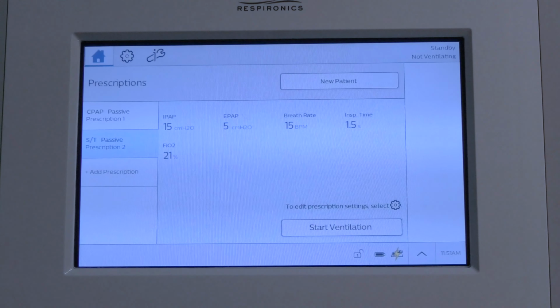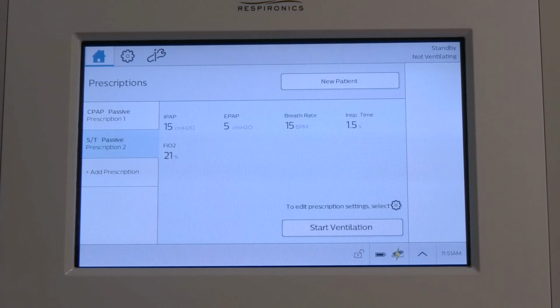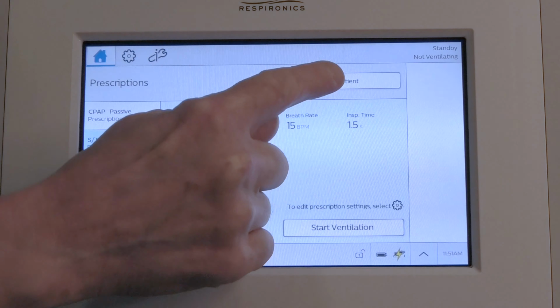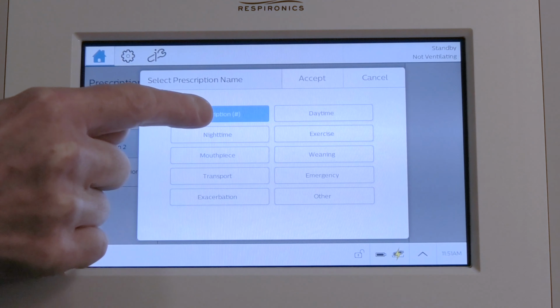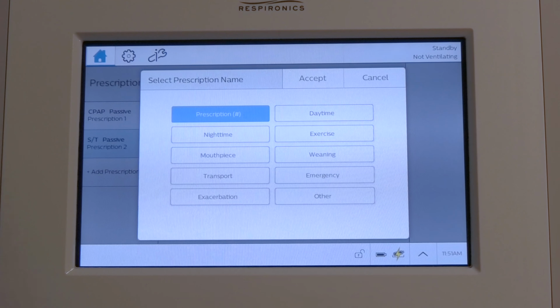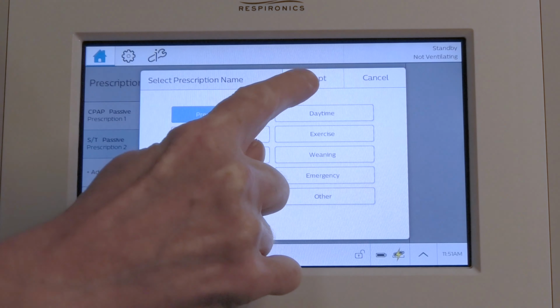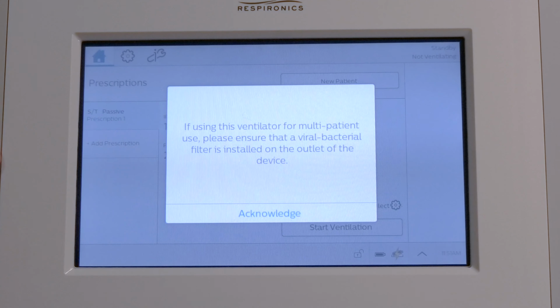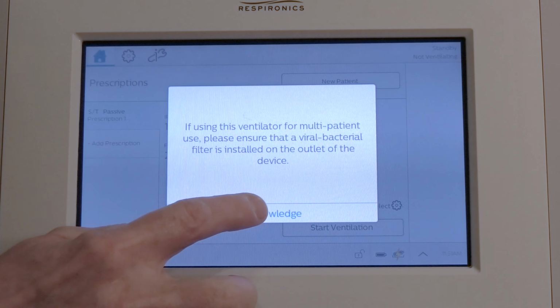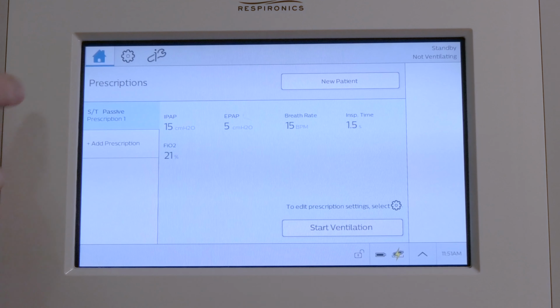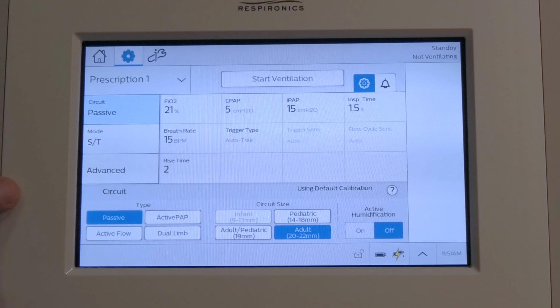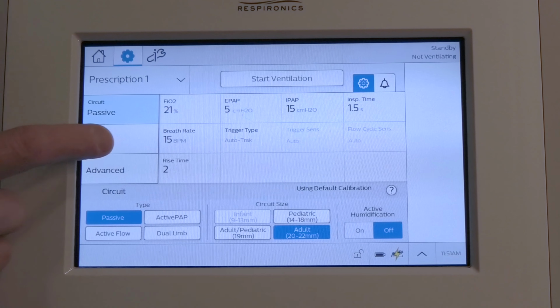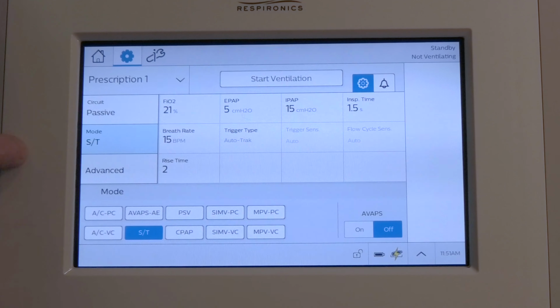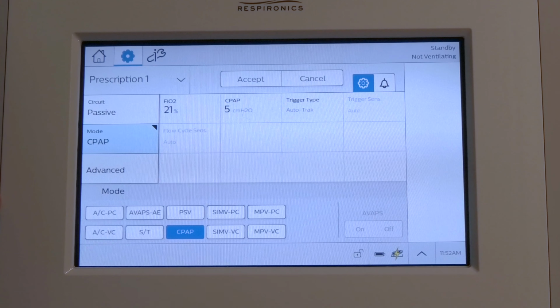If we turn the ventilator on, the Evo on, and it's in a prescription that you don't want, so if it's on CPAP and you want BiPAP, or if it's on BiPAP and you want CPAP, you go to new patient. Select that you want a new prescription, or you can give it a name if you want to. Press accept. Acknowledge that there's a filter in the circuit, which there is. And then you would go to your settings screen and set up the patient as we discussed, whether you wanted it in ST mode or BiPAP mode, or whether you wanted to go to CPAP.